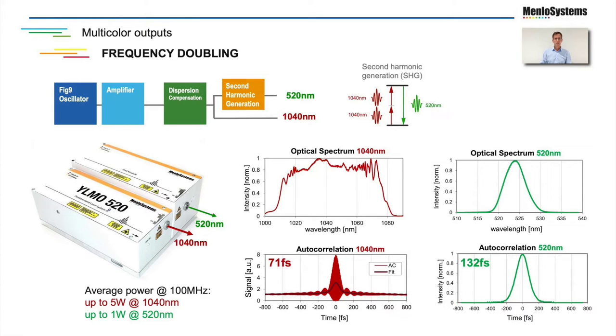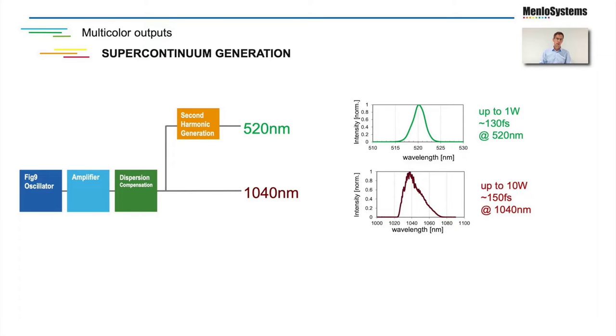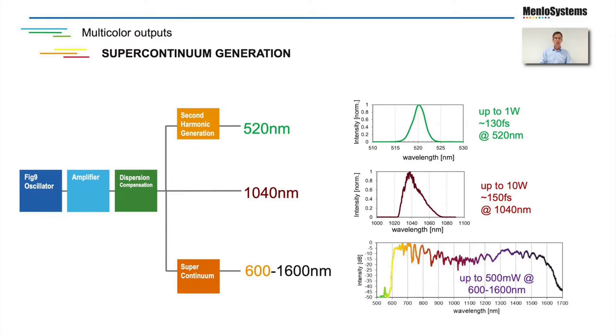Due to the same master oscillator, the output pulses at both wavelengths are synchronized and can be used, for example, for pump probe experiments. To extend the wavelength range further, we can add a supercontinuum module. By sending a part of the 1040 nanometer light into a photonic crystal fiber, the wavelength range of 600 nanometer up to 1600 nanometer can be additionally covered by generating a supercontinuum spectrum.